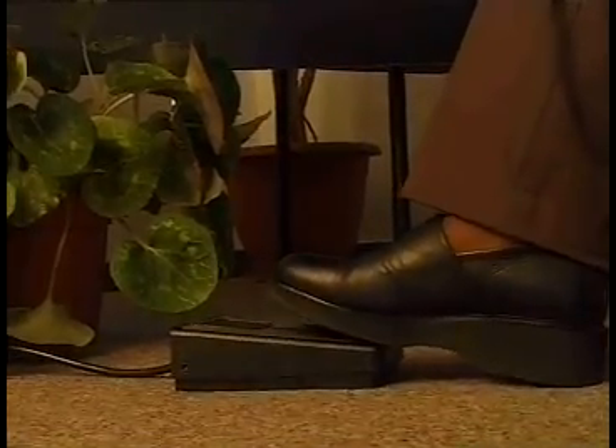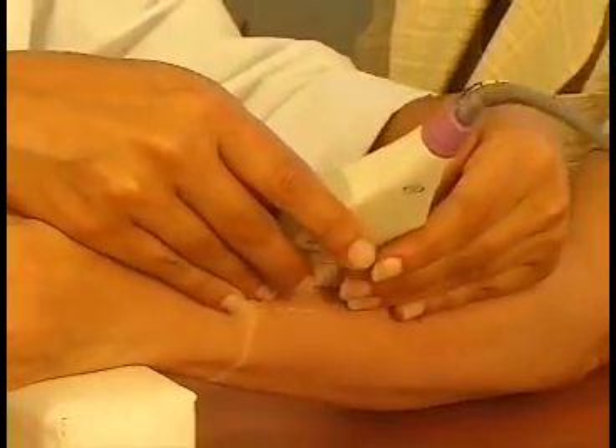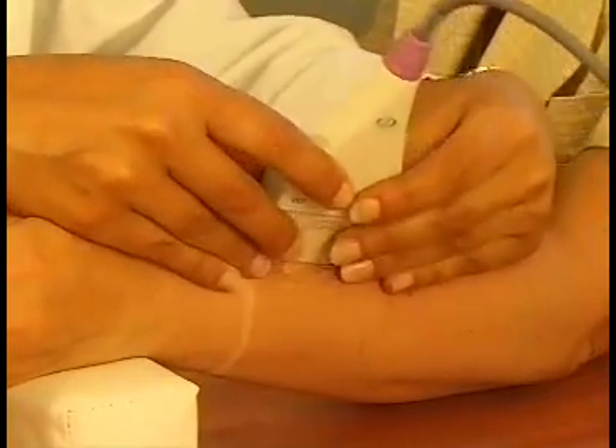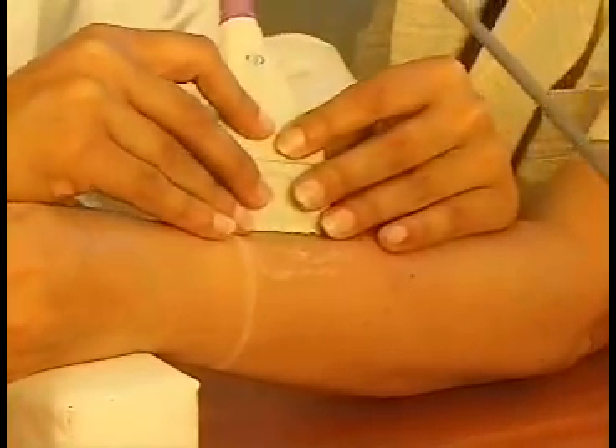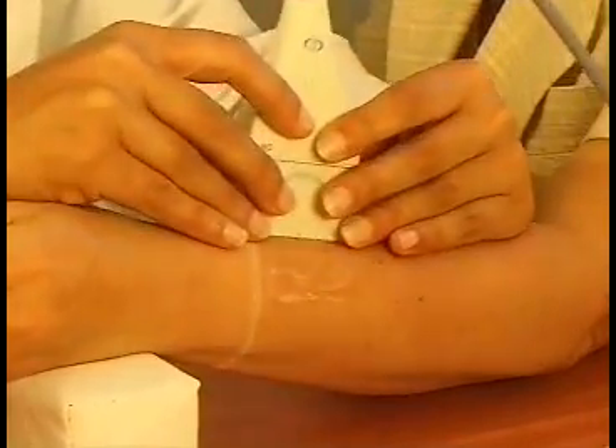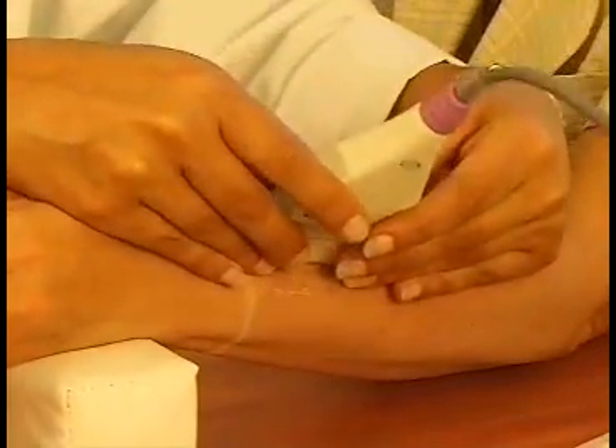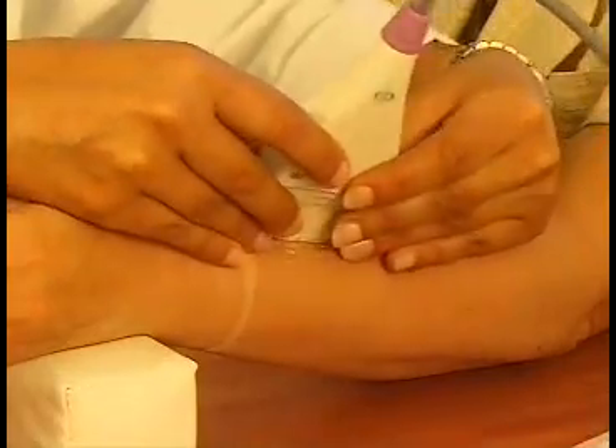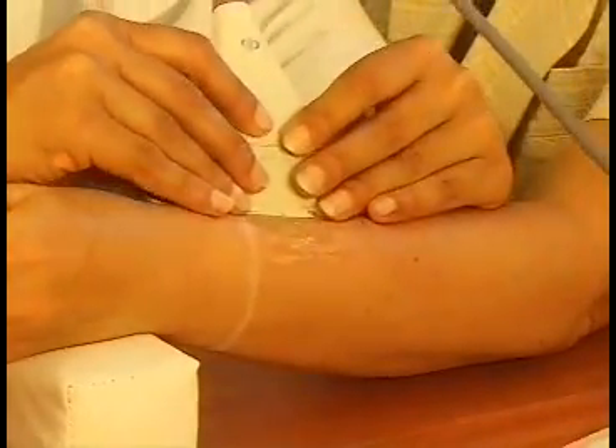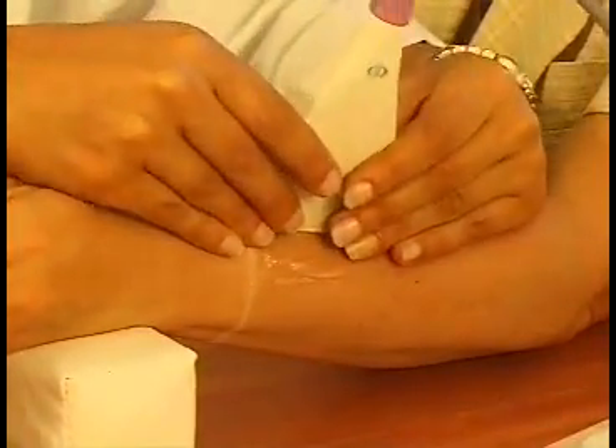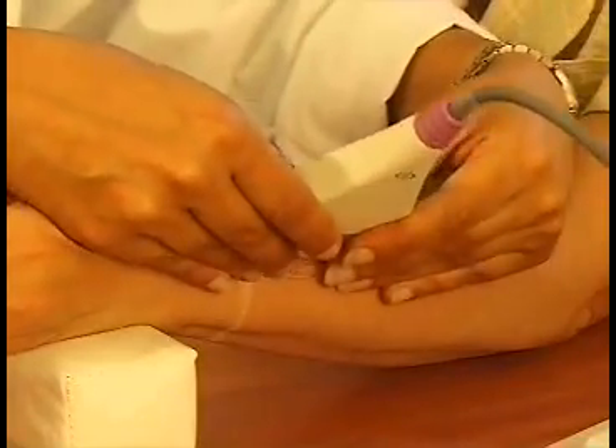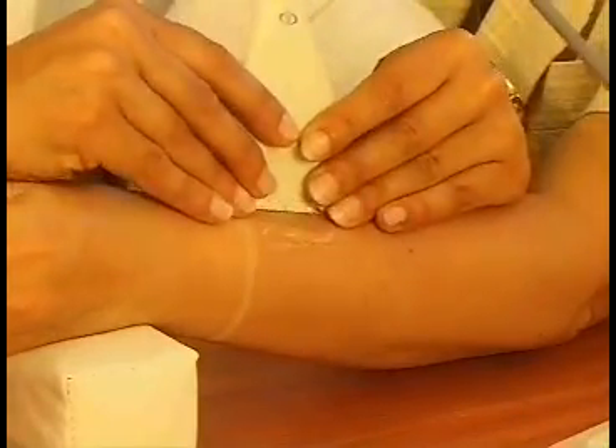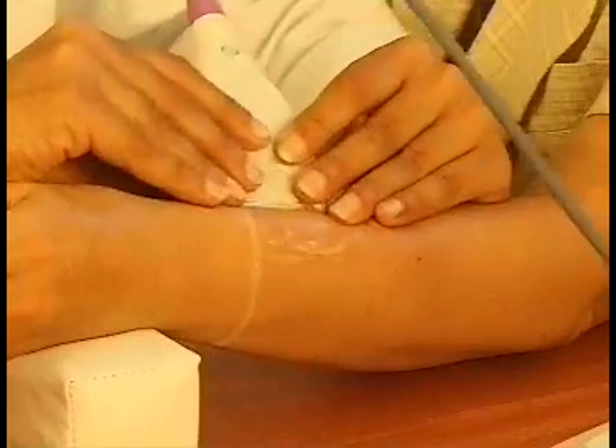Press the foot pedal and start scanning. Move the probe about 70 degrees to the lateral side and then 70 degrees to the medial side so that it scans about 140 degrees of the radius. Each scanning cycle should take about 15 to 20 seconds. Perform 3 good measurement cycles. If there is insufficient information, the system will prompt you to perform up to 2 additional cycles.